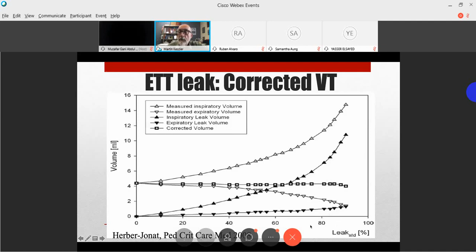And what you see here is that even up to beyond 60, 70, even 80% leak, the calculation gives a tidal volume with pretty good precision that represents the true tidal volume regardless of what's being measured. So at 80% leak, the exhaled tidal volume looks to be around 2 ml, and the inspiratory tidal volume was way crazy high. So that's a problem, right? So the clever engineers at Draeger came up with this leak compensation concept, which allows them to give us essentially the true tidal volume that gets into the baby's lungs.